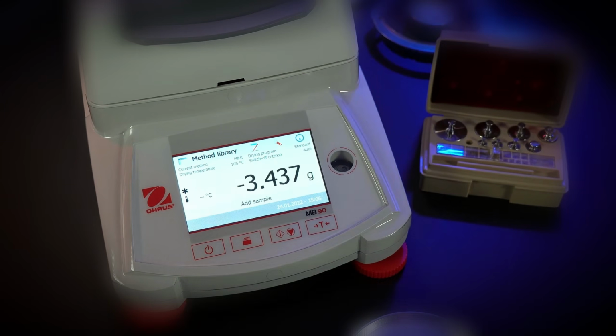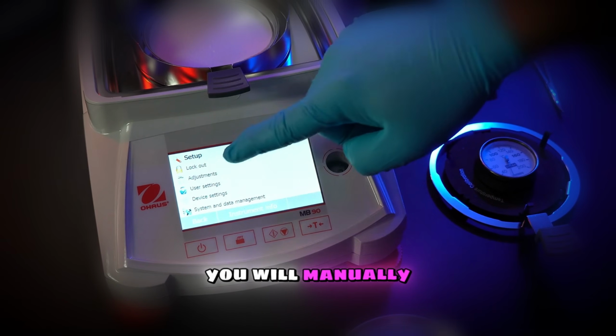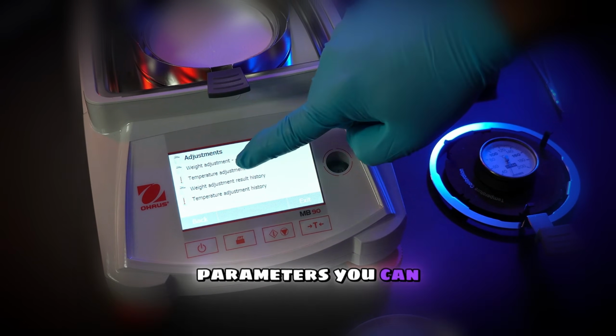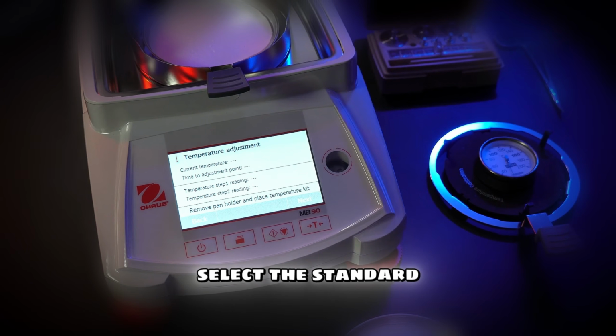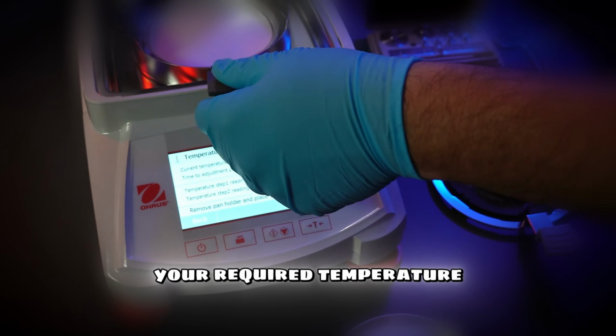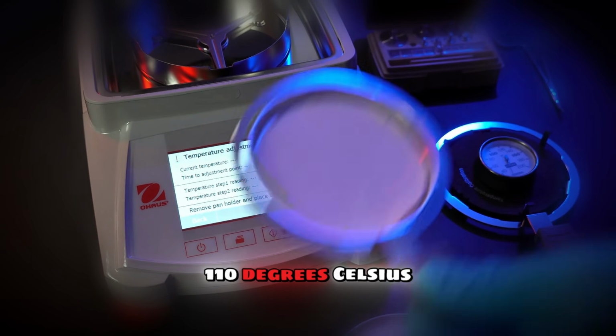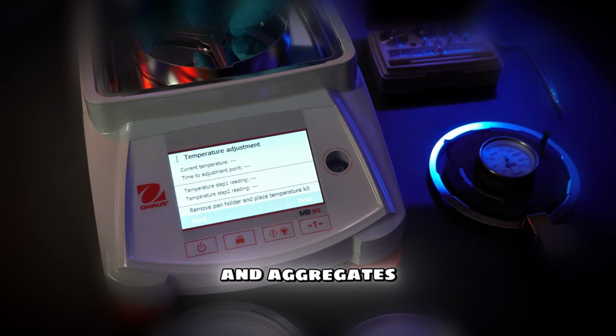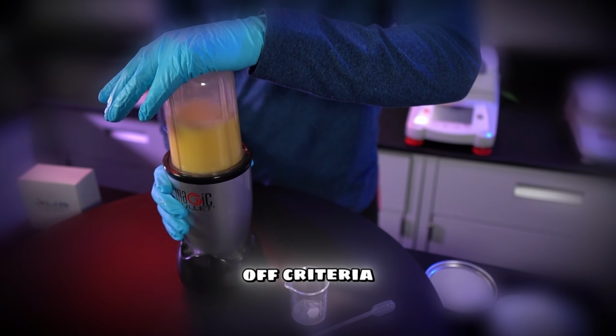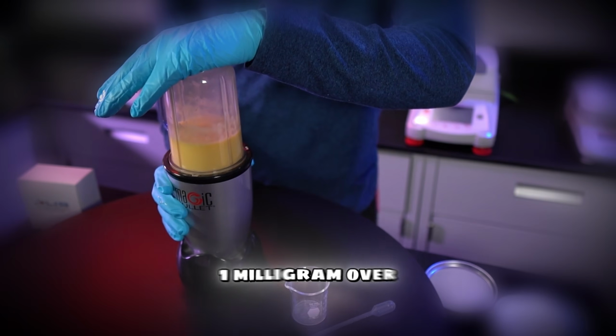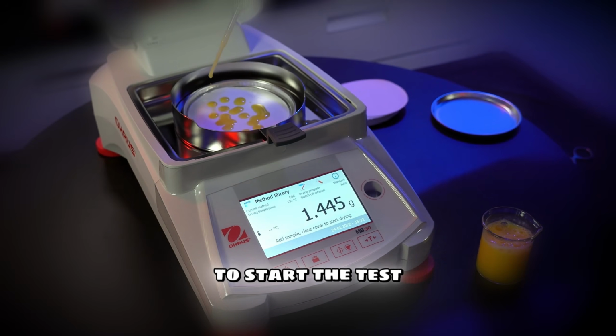On the MB90's touchscreen, you will manually input your specific testing parameters. You can select the standard drying profile and type in your required temperature, for example, 110 degrees Celsius for standard sand and aggregates. You will also set your shutoff criteria, typically setting it to stop when the weight loss is less than 1 milligram over 60 seconds. Close the lid to start the test.